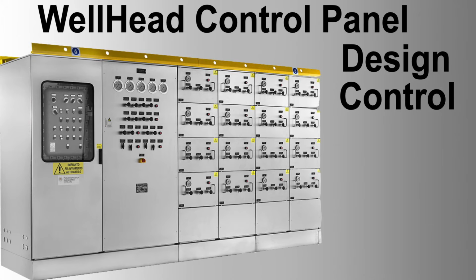Control loop specifications: pressure control loop. Sensor: pressure transducer, range 10,000 psi, accuracy 0.1% FS. Actuator: hydraulic or electric control valve, 4 to 20 milliamps control signal. PLC RTU: PID control algorithm, set point adjustment via HMI SCADA. Feedback: real-time pressure data to PLC RTU. Alarm: high-low pressure alarms. Shutdown: ESD if pressure exceeds critical limits.